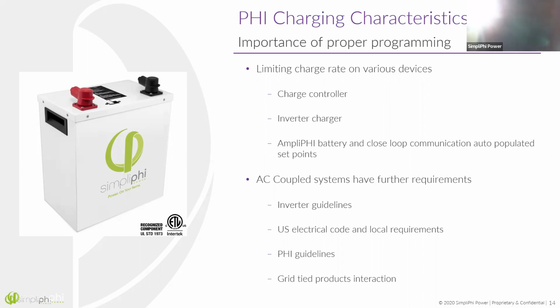AC coupled systems have further requirements. We have to be a little bit more strict on AC coupled systems. The reason for this is that AC coupled systems are not as easy to throttle back as DC coupled systems are. An MPPT controller on DC coupled systems can easily be set up to only allow a certain amount of current. AC coupled systems are basically on or off.